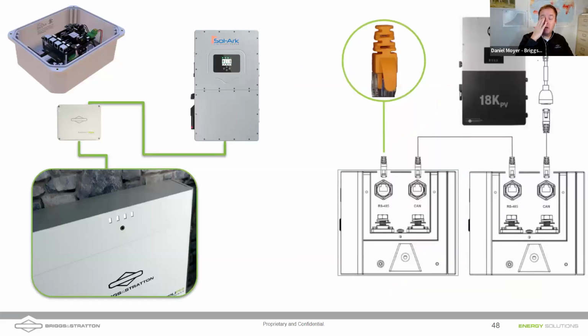When we're wiring the EnergyTrack gateway, we're going to come out of the inverter, out of the back CAN, flow into the EnergyTrack. Out of the EnergyTrack gateway, we're going to flow down to the batteries. If we have a site that's not going to be leveraging the EnergyTrack gateway, we're going to come directly out of the battery controller on the top of the battery. That's what you're looking at of a side picture here. Out of the CAN port, through a crossover dongle, directly into the inverter, and we're going to have a terminating resistor in the last battery in the stack, or in the first battery if there's only one stack, to close off that closed loop communications.